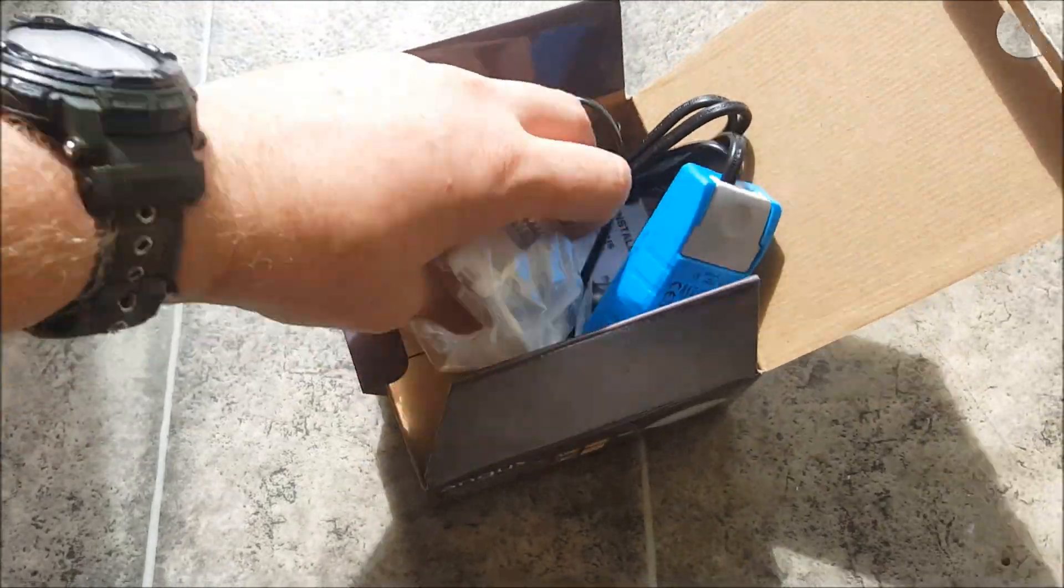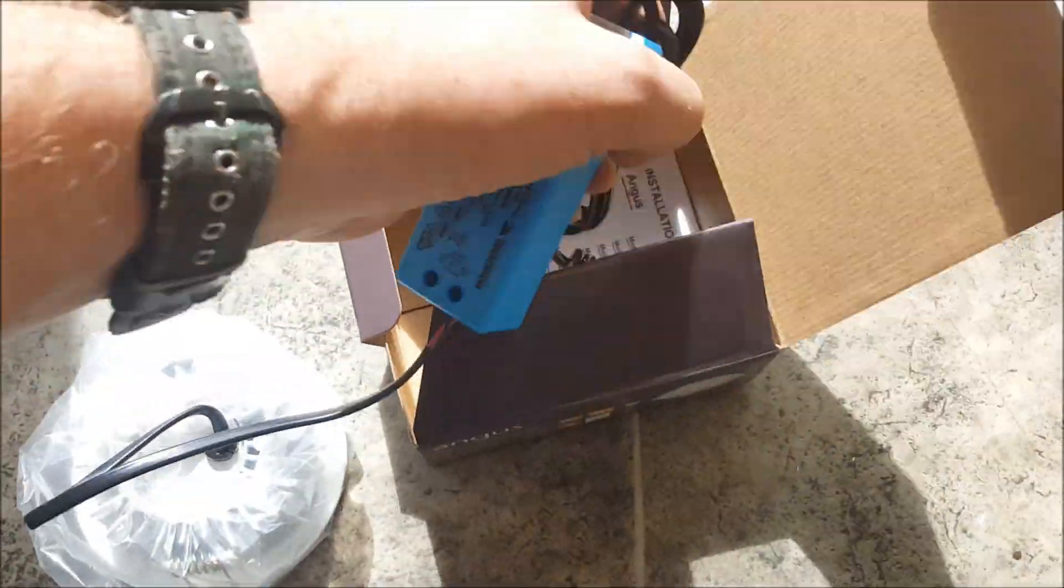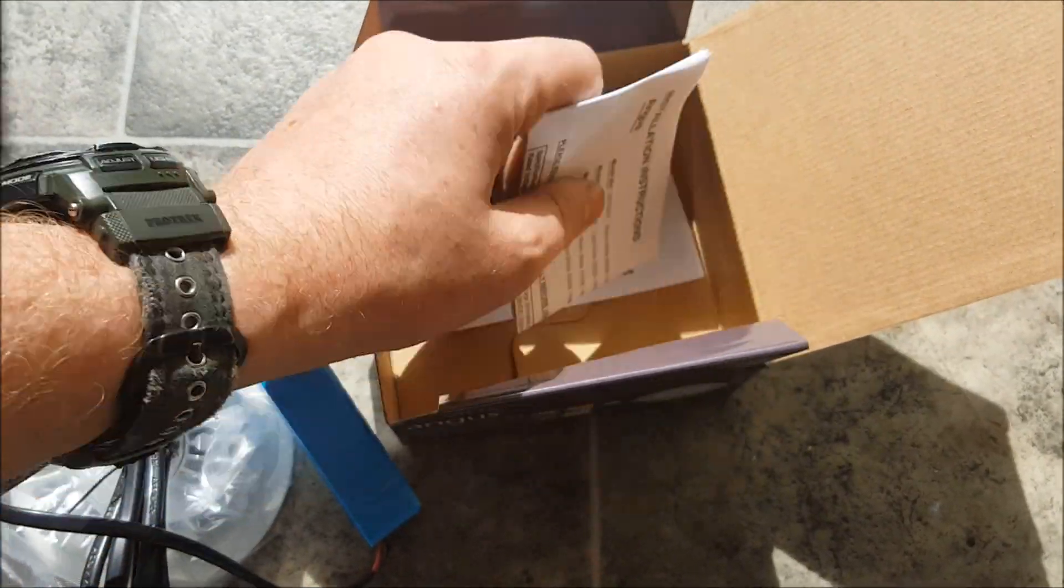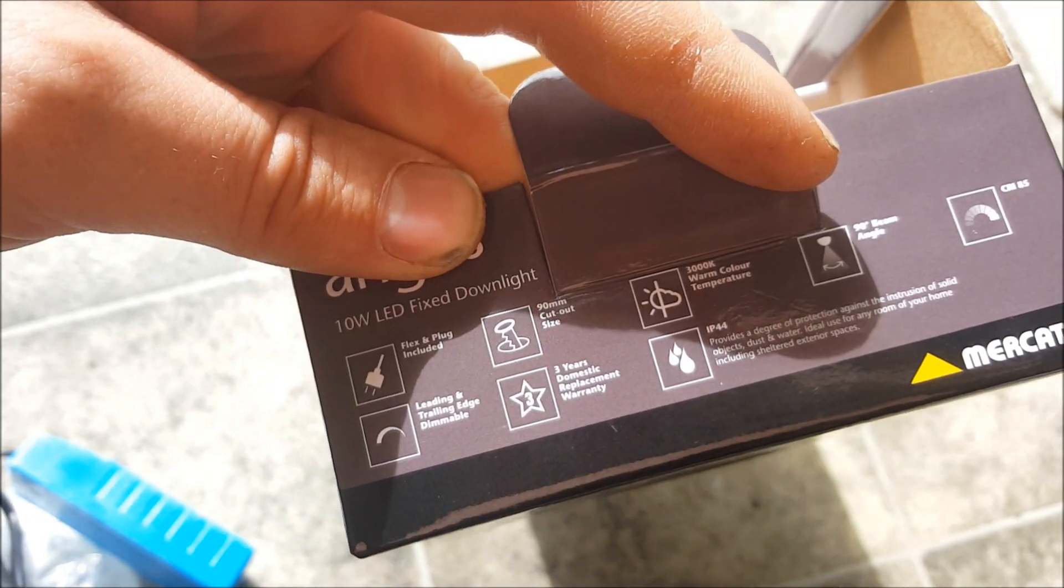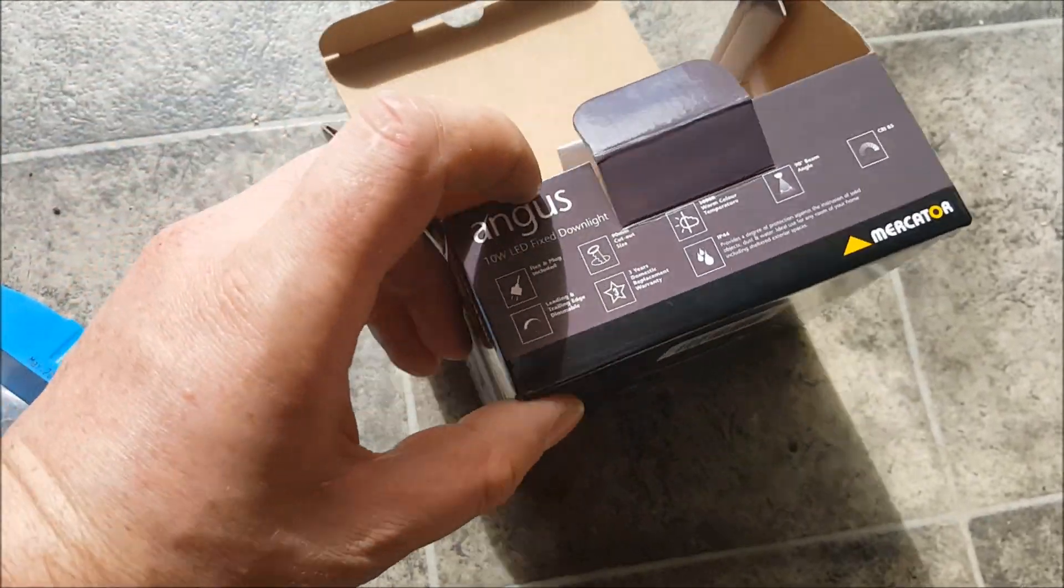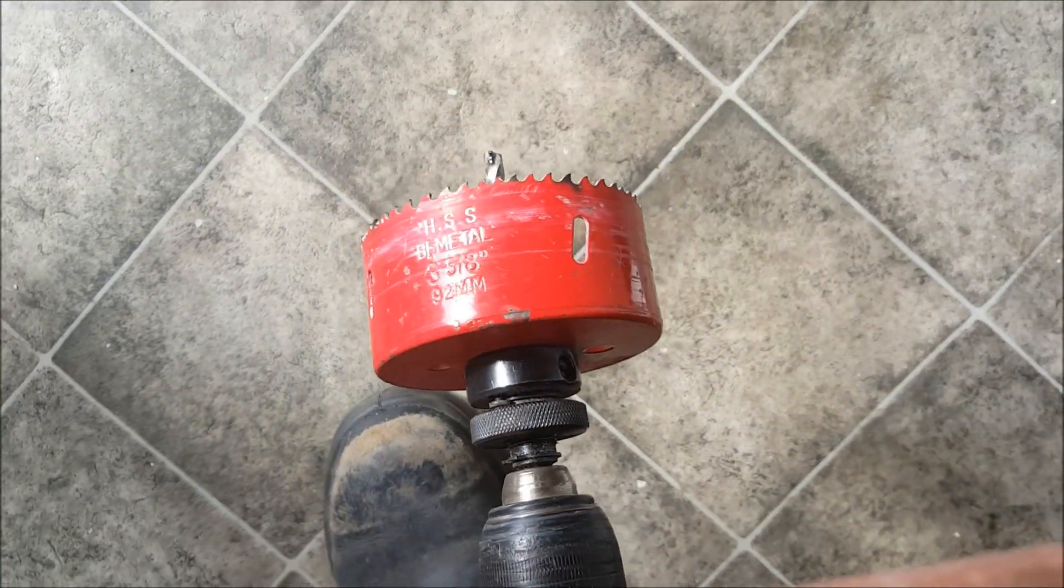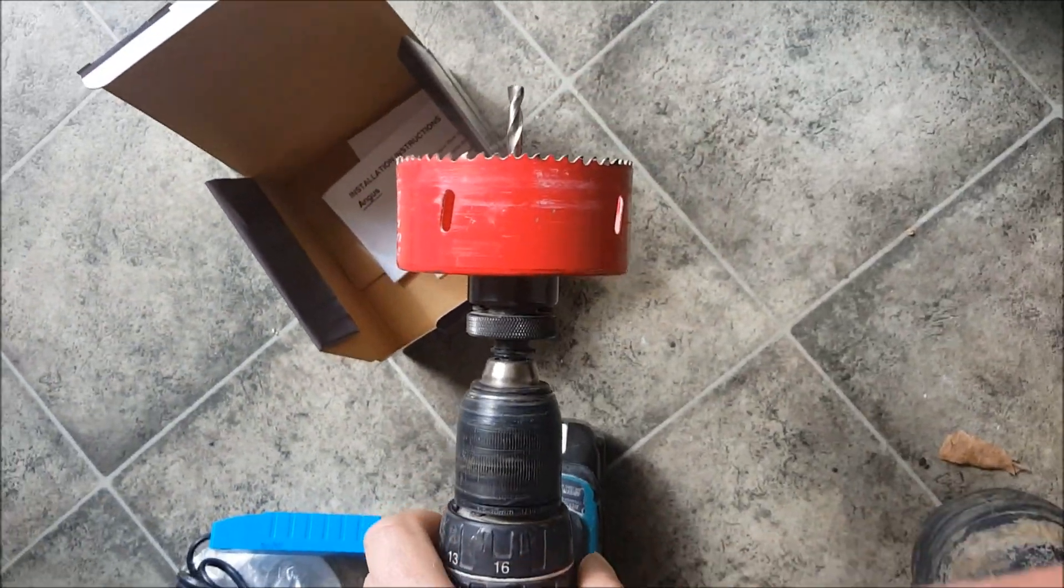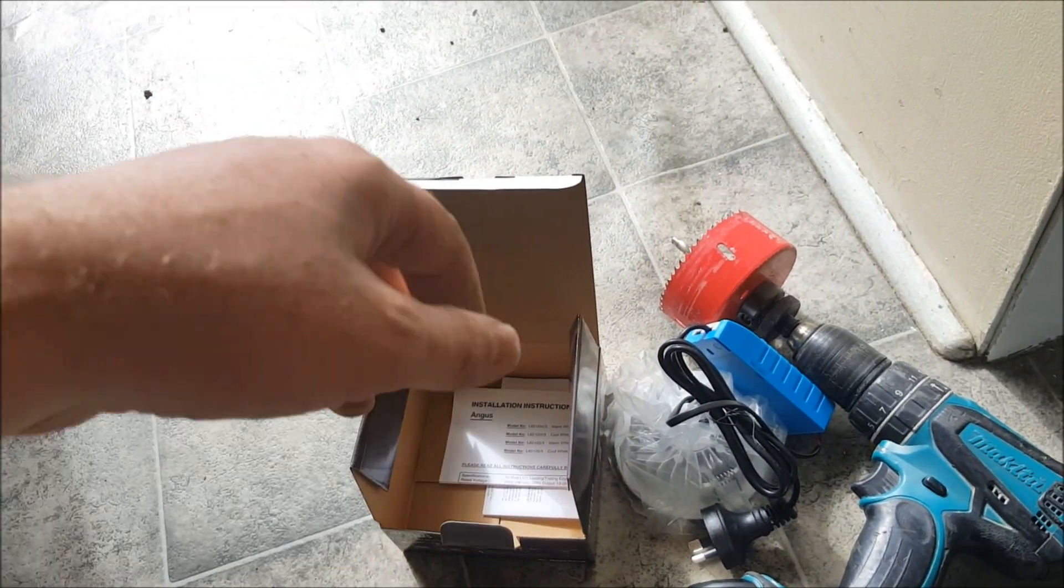So one of the first things you want to do is check what the cutout of the downlight is and get a hole saw to that effect. This one here, it says on the box it's a 90mm cutout size and I have got a 92mm hole saw just for an extra bit of room around it so you can slide it in pretty easily.